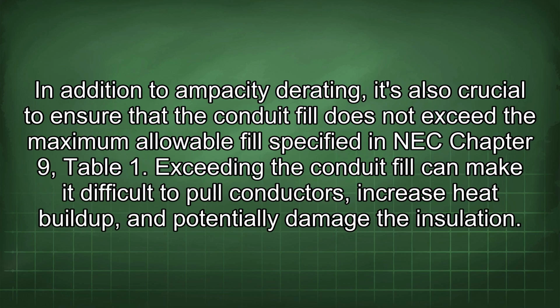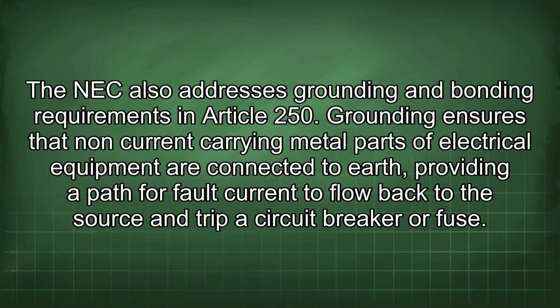In addition to ampacity derating, it's also crucial to ensure that the conduit fill does not exceed the maximum allowable fill specified in NEC Chapter 9, Table 1. Exceeding the conduit fill can make it difficult to pull conductors, increase heat buildup, and potentially damage the insulation. The NEC also addresses grounding and bonding requirements in Article 250. Grounding ensures that non-current carrying metal parts of electrical equipment are connected to earth, providing a path for fault current to flow back to the source and trip a circuit breaker or fuse.